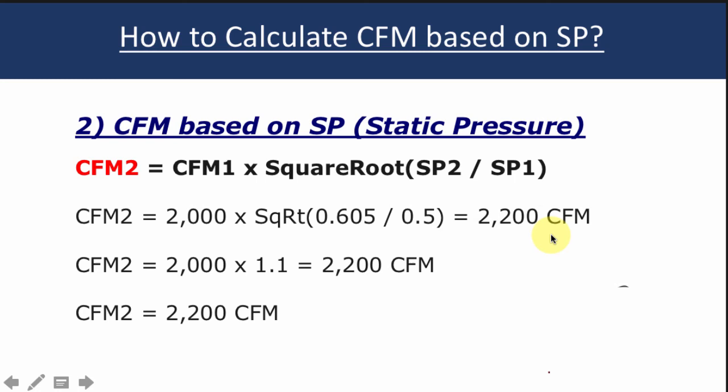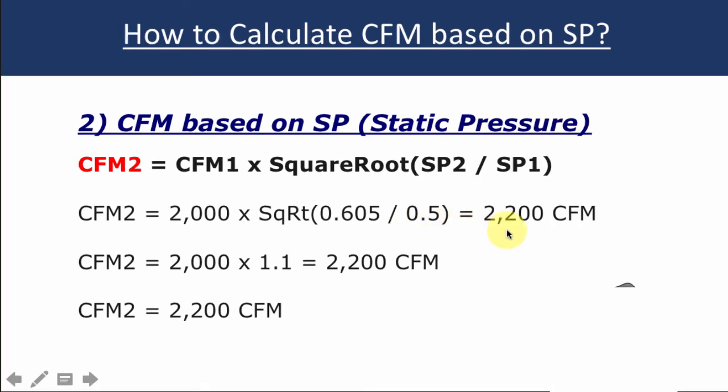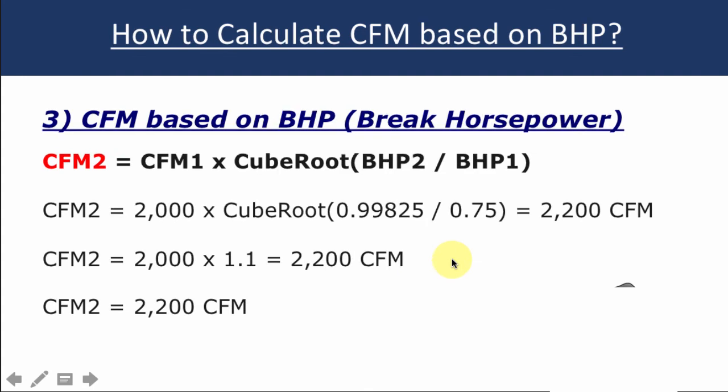Now with static pressure, it's a little different. Now you're dealing with the square root of the static pressure new over the old. So just work these numbers out, pause the video, work these formulas, look at the formula and practice them. They're pretty simple. In this case, the 2000 CFM of existing and let's say we're increasing the static pressure to 0.605 over the existing static pressure would tell us that you would have 2200 CFM. So just work these formulas out.